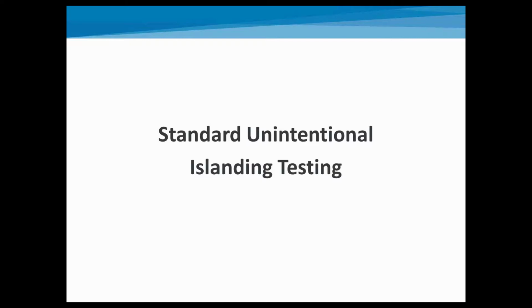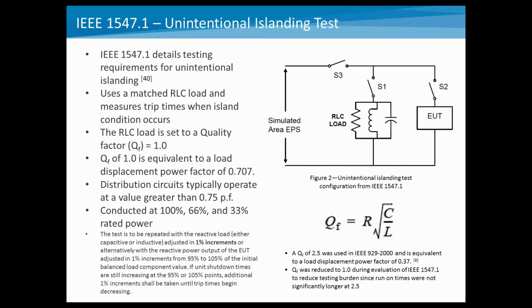Okay, so that talks about the variety of different techniques used to detect and mitigate unintentional islands. I'll talk now a little bit more about standardized testing that's done in this area. Inside of 1547.1, there's an unintentional island test that basically defines how pieces of equipment are tested to evaluate for unintentional islanding capability. The thing to realize about this test is that it is only done on a single inverter or a single distributed generator in this case.